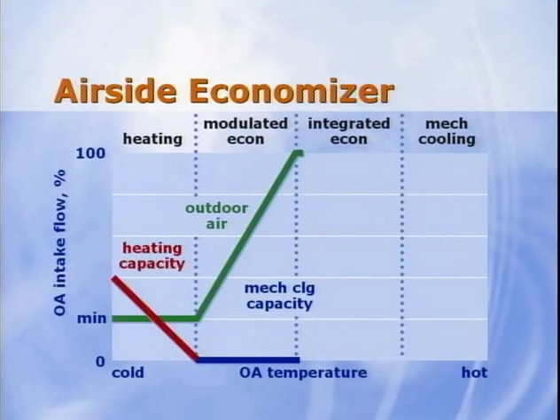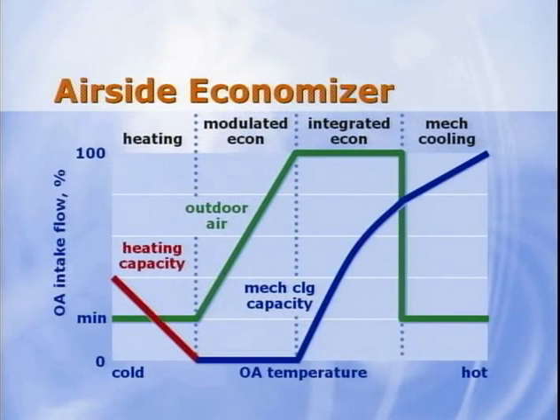When the temperature of the outdoor air rises above the current supply air set point, the system needs more cooling capacity than the outdoor air alone can provide. In this integrated economizer mode, the outdoor air dampers remain wide open and the rooftop unit activates compressors to provide the balance of the cooling capacity needed. This also saves energy by reducing the cooling load on the compressors. Eventually, as it gets hotter outside, the outdoor air damper is closed to minimum position and the compressors provide all the needed cooling. This decision to disable economizer operation is typically made automatically by comparing the condition of the outdoor air to a set point called the high limit shutoff setting.